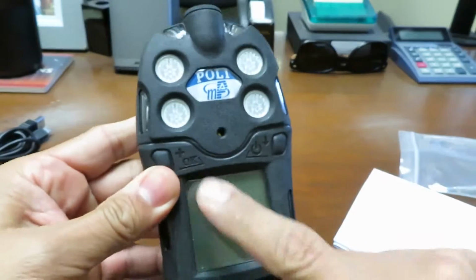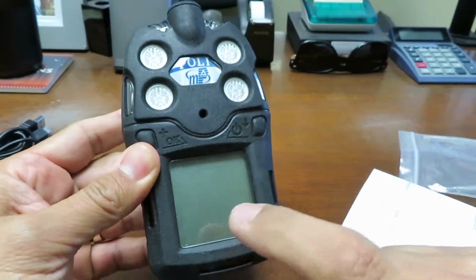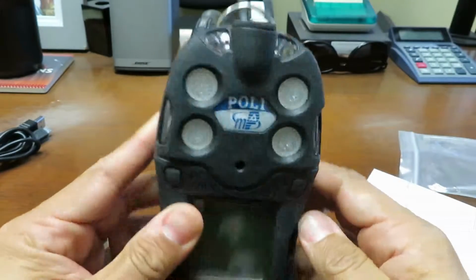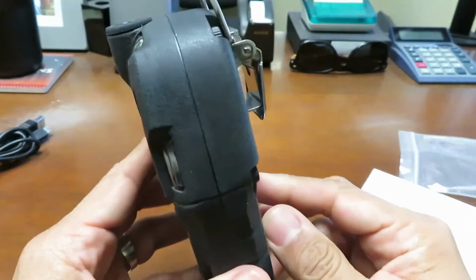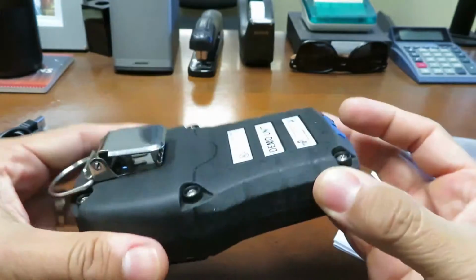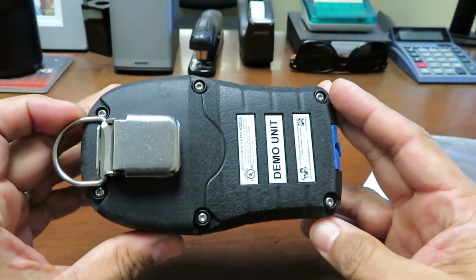The direct readout on this unit gives real-time reading of gas concentration, especially in pumped mode. It shows the PID measurement gas and correction factor, and it has a man-down alarm that can be turned on and off.